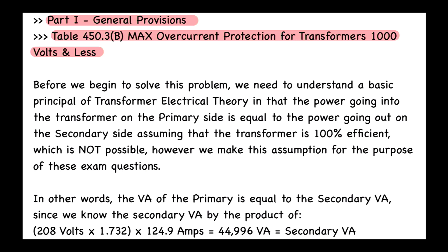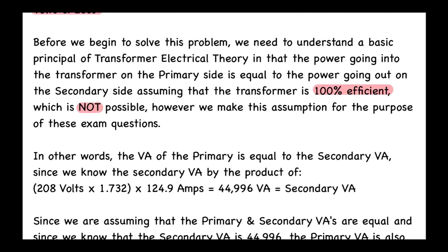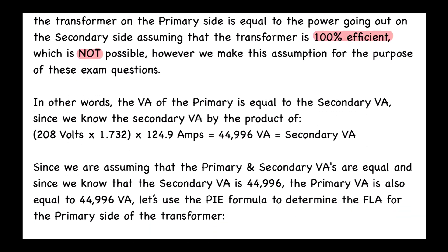Before solving this problem, we need to understand a basic principle of transformer electrical theory: the power going into the transformer on the primary side is equal to the power going out on the secondary side, assuming 100% efficiency. This is not actually possible, but we make this assumption for exam purposes. The VA of the primary equals the secondary VA. Since we know the secondary VA — 208 volts times 1.732 for three-phase times 124.9 amps — that gives us 44,996 VA.